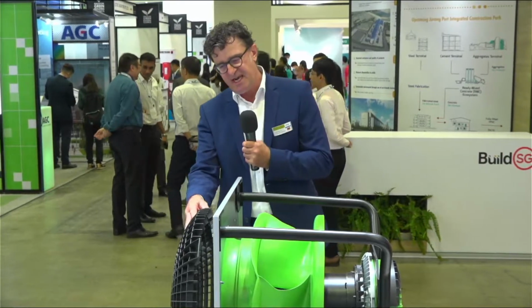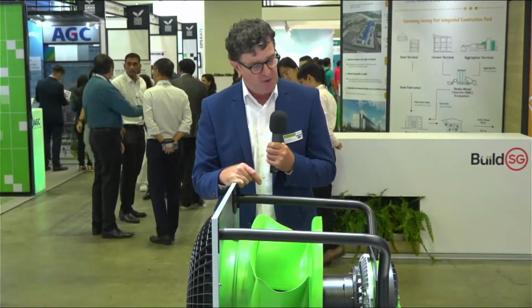On the suction side, we have an additional part that is a flow grid that helps to reduce the turbulences towards the impeller, and that also helps to reduce the noise. Here we have sizes from 310 up to 630. This is more or less giving an airflow of 20,000 cubic meters per hour at a maximum pressure of 2,000 pascals.